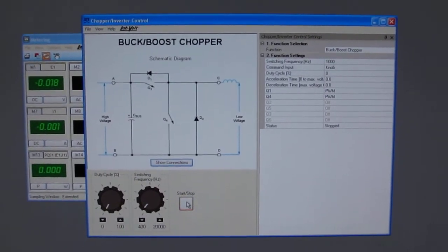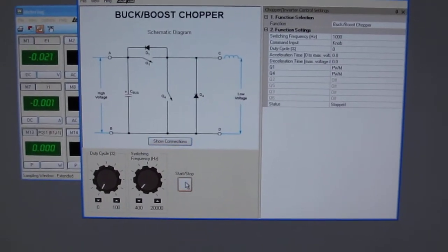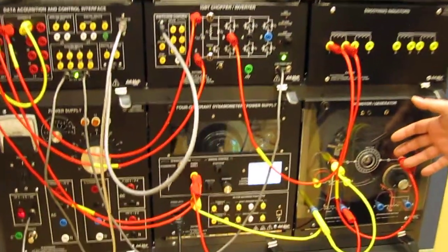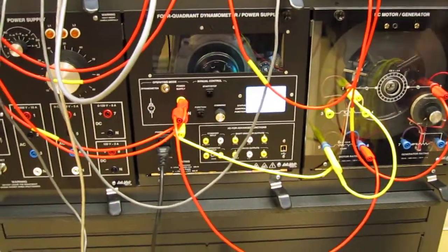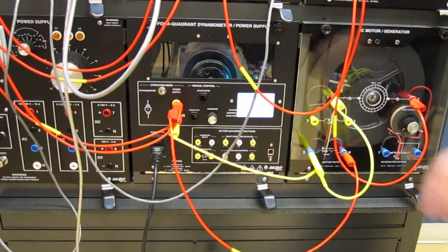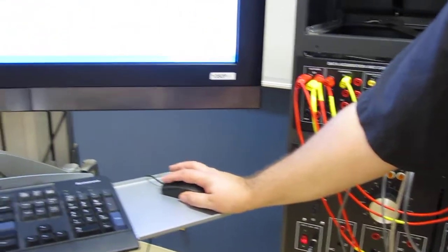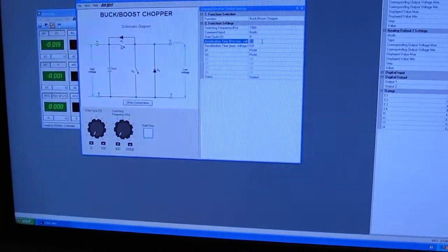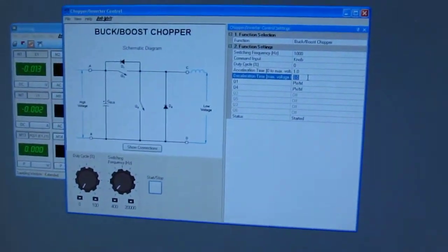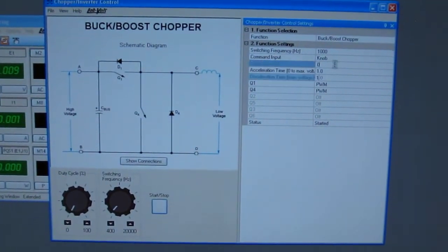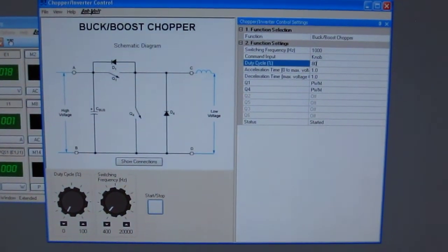So when I press start on that and start on the power supply, right now I have no speed at all because my duty cycle is at zero. So let's say I want to go to a duty cycle of—I'll give it some acceleration and deceleration time, let's say one second for acceleration and deceleration. So I go to a duty cycle of 80%.